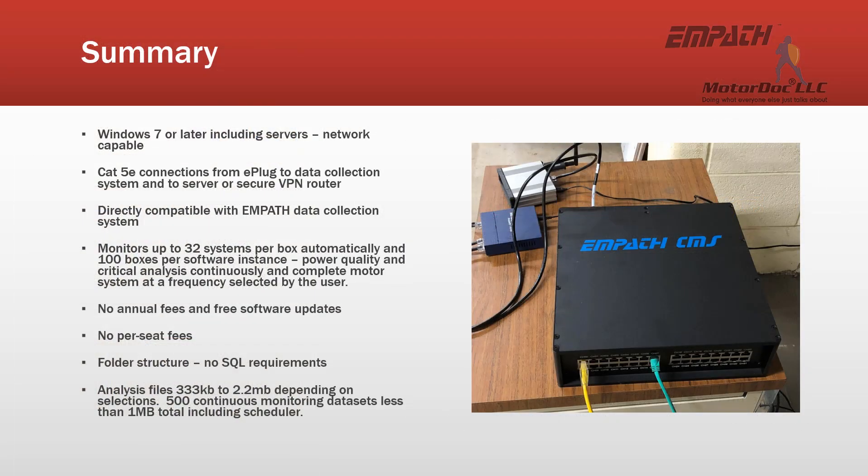The online system, or continuous monitoring system, uses Windows 7 or later, including any Windows-based server, or SCADA network capability. It uses Cat5e connections, everything from the e-plug to the data collection system, and to the server or secure VPN router for wireless capability. Directly compatible with the EMPATH data collection system, as well as another manufacturer's equipment. It monitors up to 32 systems per box automatically — that's 32 motors or transformers or other three-phase inputs per box — and 100 boxes per software instance.